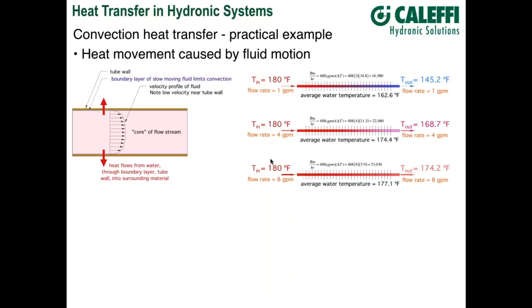Let's bump it up to 8 GPM on the same fin tube. The outlet temperature does increase, not quite as much as before. Our average temperature went up roughly about three degrees Fahrenheit. Output went from 22,000 to about 23,000 BTUs per hour. We continue to increase heat transfer as we increase flow rate, but we're seeing a diminishing rate of increase — yes, it's going up, but by smaller and smaller amounts.